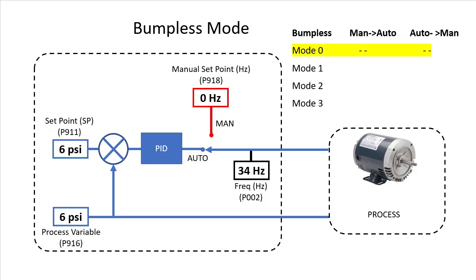Bumpless mode 0 is where the bumpless mode is turned off and PID does everything it can to get to the set point as fast as it can, which for some processes can be dangerous.